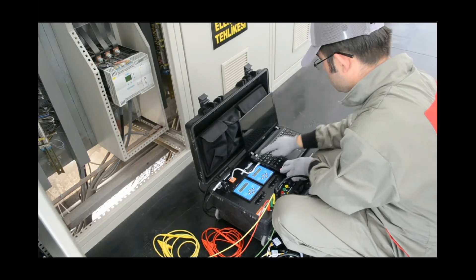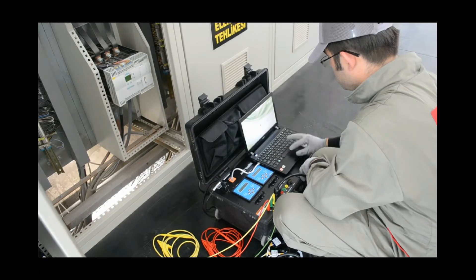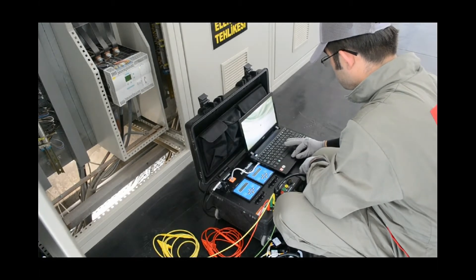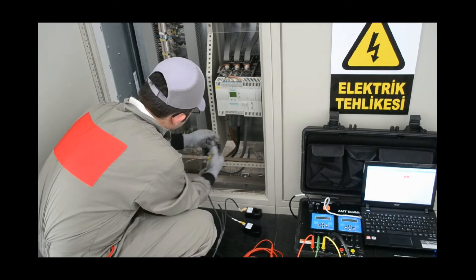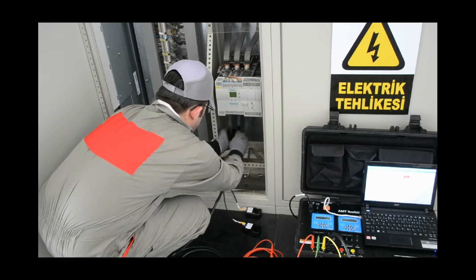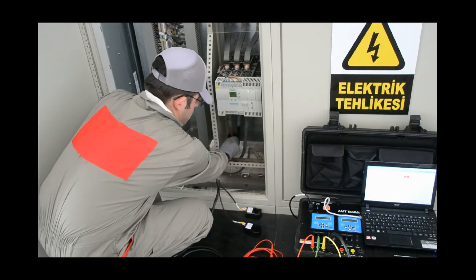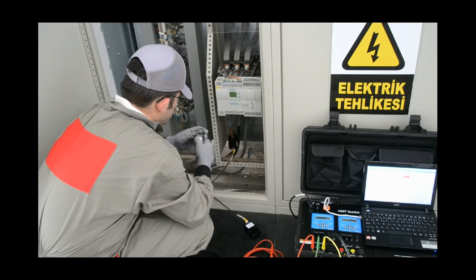The total duration of the test is approximately 45 minutes to 1 hour, including the installation, stopping and starting the motor, data acquisition and dismantling processes. At the end of the testing period, Toolkit generates a condition assessment report which indicates existing faults in the system, recommended corrective action and the effects of these faults on energy efficiency.